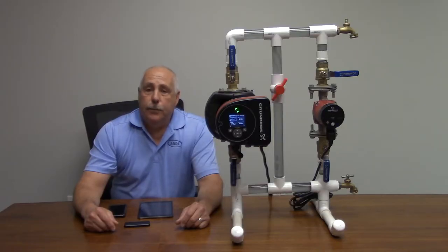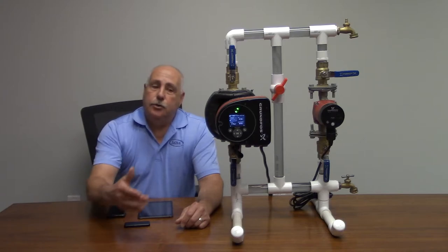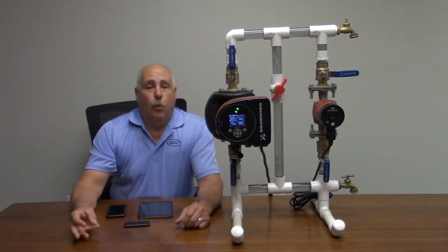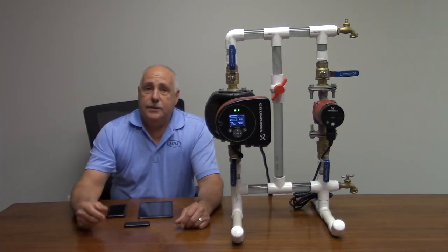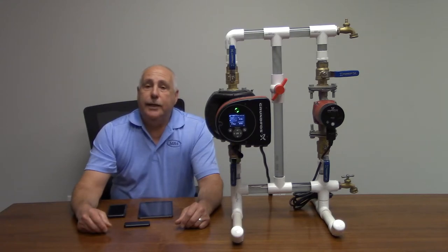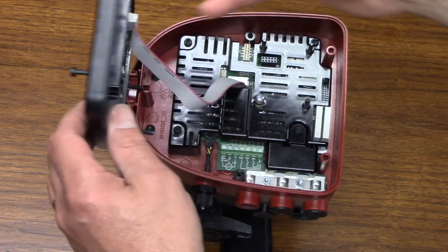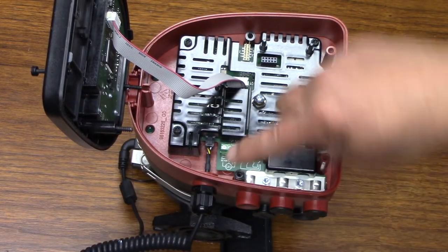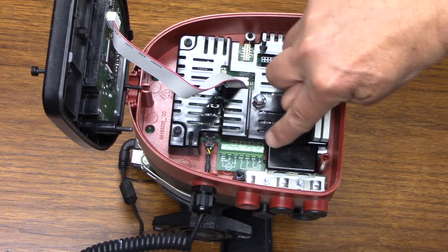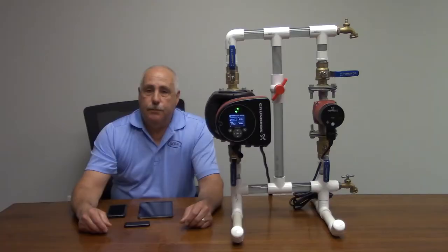The third option for communication is internally to the unit. You can set up one analog input, so remote sensor. You can do two relay configurable outputs like if it's closed, it's an alarm, the pump is running, whatever you want. You get to play with both the common, normally open, and normally closed of two relays. The last part is three digital inputs: start, stop, minimum curve, and maximum curve.